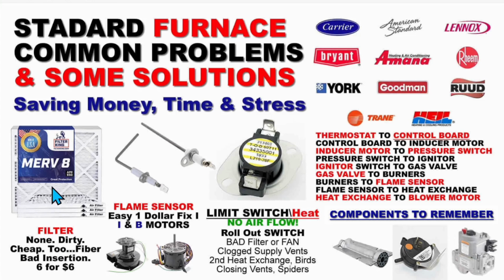But a mistake that people make with filters is buying cheap filters that let too much in. Try to find an in-between filter and then make sure you insert it correctly so it's taking the air up and out of your furnace and not blocking it in. I've seen these things put in backwards and that creates airflow problems, and that's a big issue.